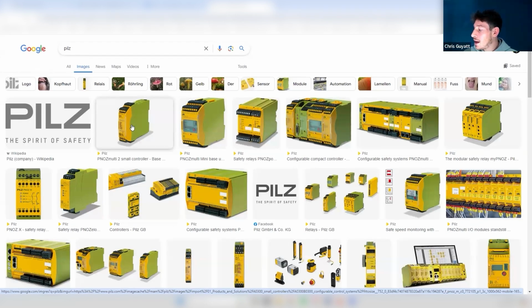You do the risk assessment in a BMS project, and it never warrants the need for a safety relay. So we don't need to use one of these in this project, but in another industrial project where there's moving machinery, that circuit we just went through may need to go back to a safety relay to verify that it's in the correct state, healthy or not healthy. I think these are tested to a very high level, so there's no chance of a malfunction which could lead to someone losing their life or a limb.